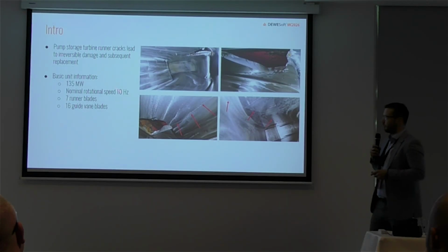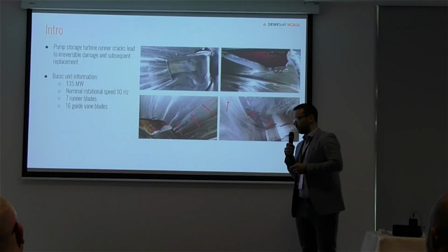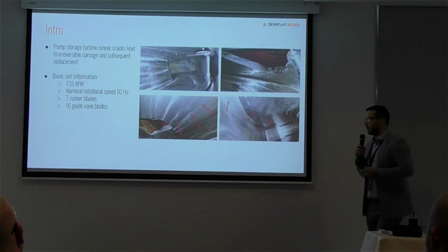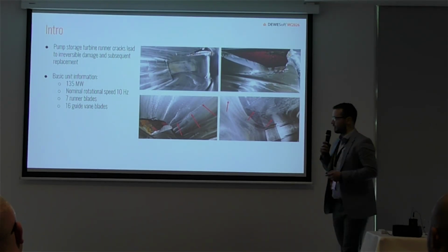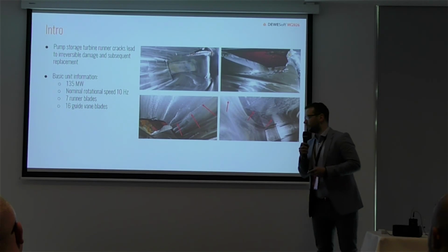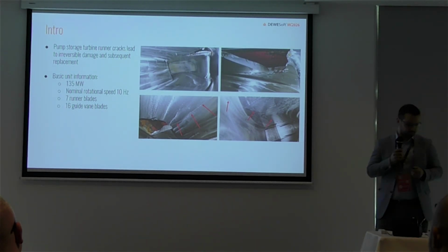And here is some basic information about the unit, which will be significant for our analysis. The nominal rotational speed is 10 Hertz, and this turbine runner has 7 runner blades, and there are 16 guide vane blades on this unit.